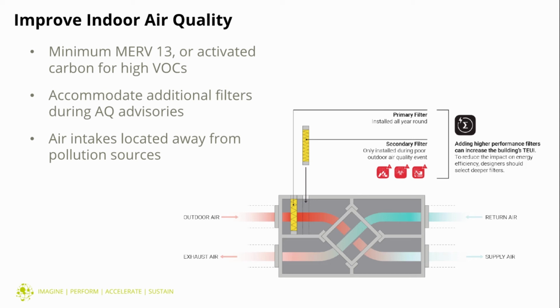Forest fires, we know, are increasing and are going to become more and more of a challenge. So understanding how we can mitigate that? It's only for a short period of the year. One of the benefits of air handling units and heat recovery ventilators is that they're designed to operate with a dirty filter, which means they have a bit more capacity when you put a clean filter in. And so there's an opportunity to take out the more typical MERV 13 filter and perhaps put in an additional filter or even a secondary filter that could provide a higher degree of filtration without dramatically impacting the output of the unit and the ventilation flow rates to the building.